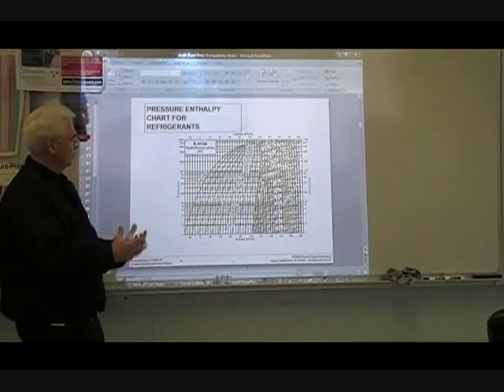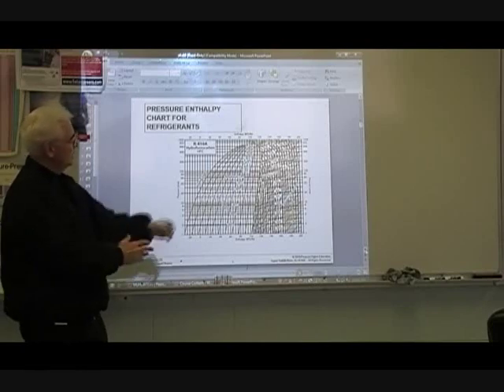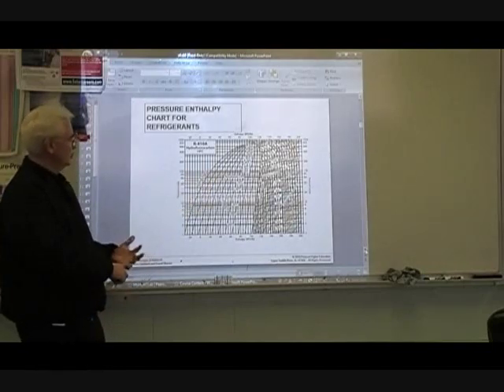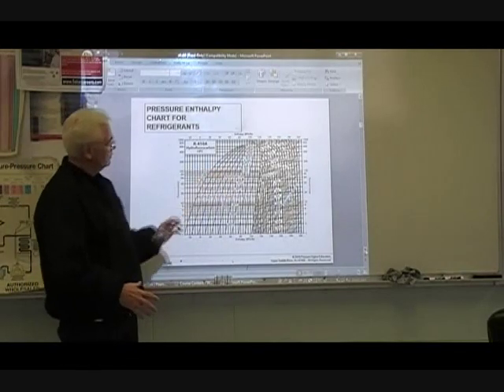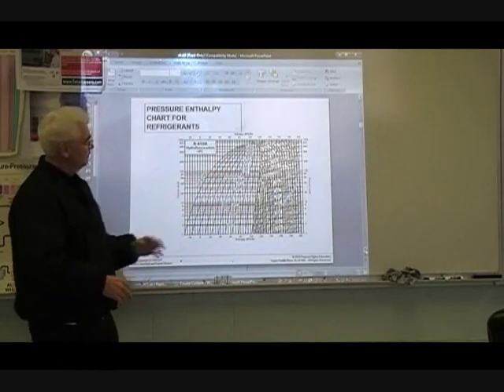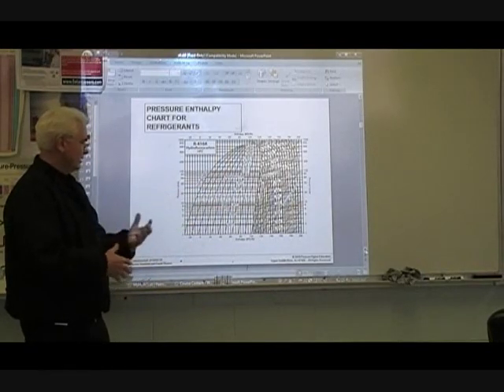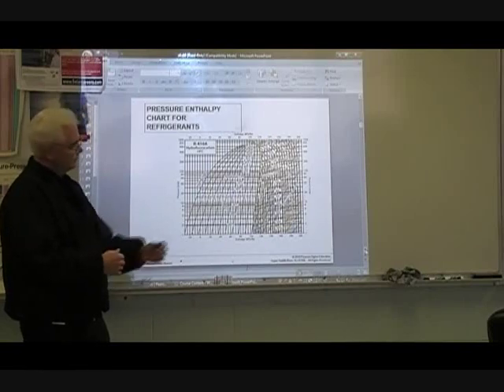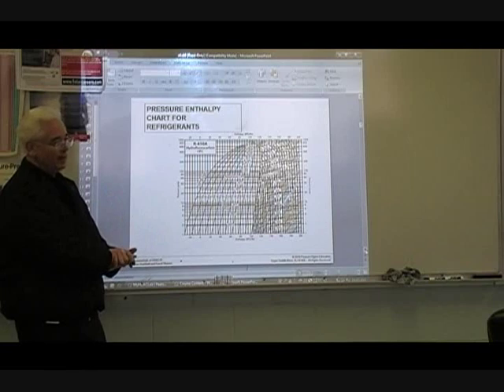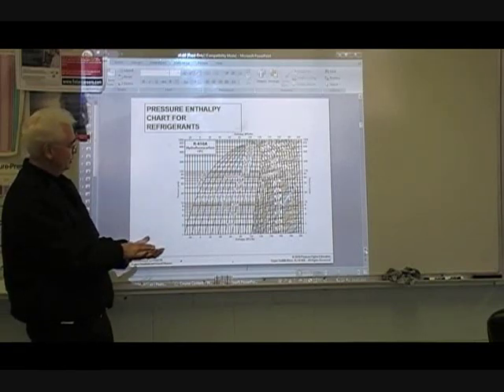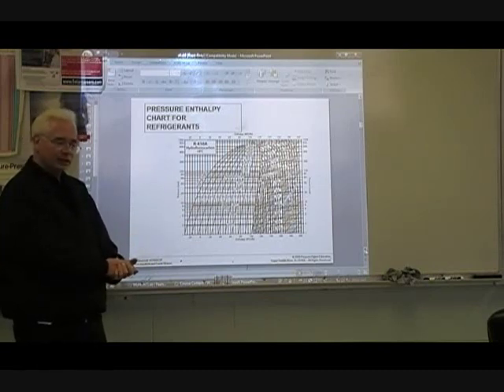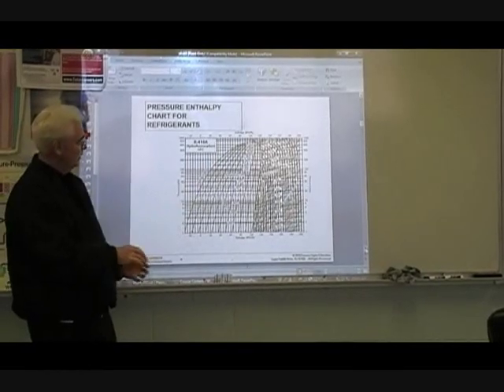That's why we can't calculate volume directly. When you put manifold gauges on a refrigeration system, you're reading pressures and converting pressure to temperature, taking temperature measurements on your suction line and liquid line to calculate superheat and subcooling. You're not measuring volume per se. However, with the pressure-enthalpy diagram you can look at what's happening volumetrically. As a service technician, you'd probably never use this — the pressure-enthalpy diagram is used to design refrigeration systems. If you're an engineer designing a system, you'd use it.